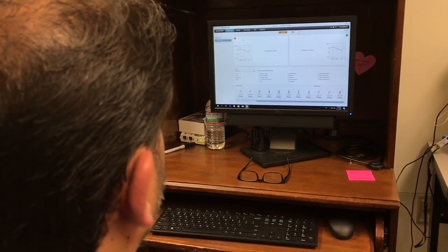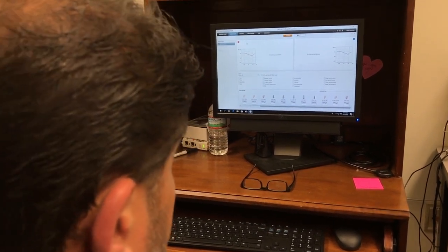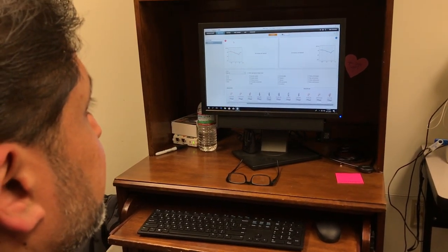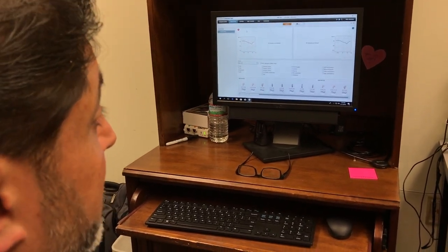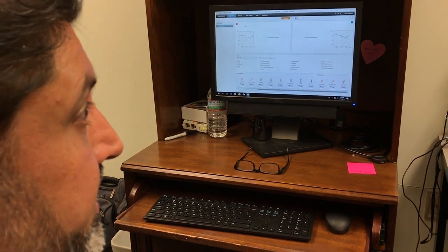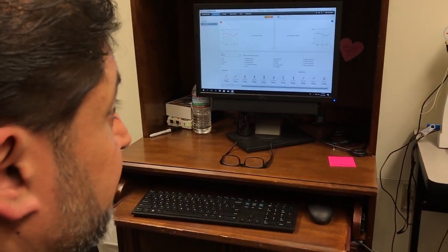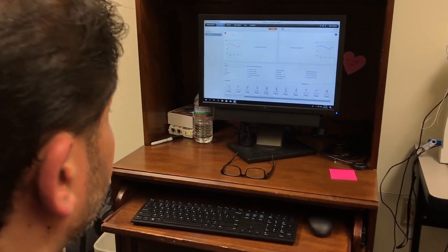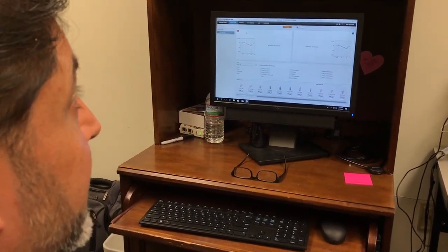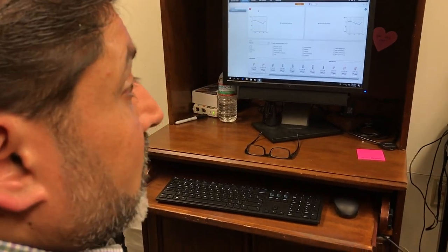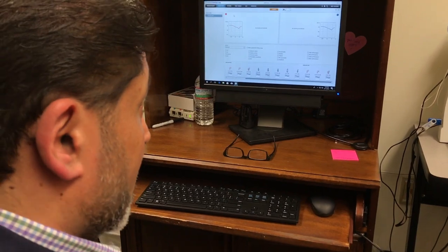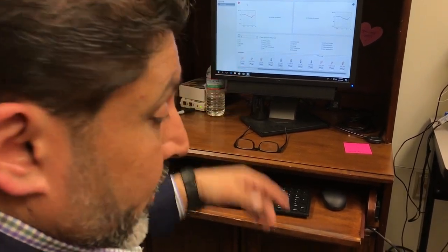Okay. So I'm starting to think more acoustics here. How are we going to get those highs? How are we going to get him those high frequencies that he needs, because he wants to hear that whistling sound. We could look at an ear hook. We could look at tubing. What else can we do that will give us highs? You can bell. What else? Venting. Venting will get rid of some of the lows. We have a problem here because he's got thresholds near 40.